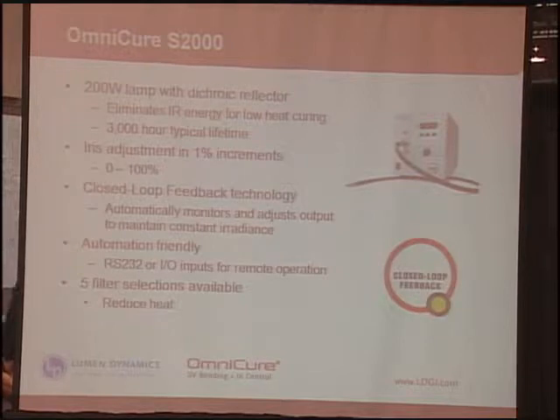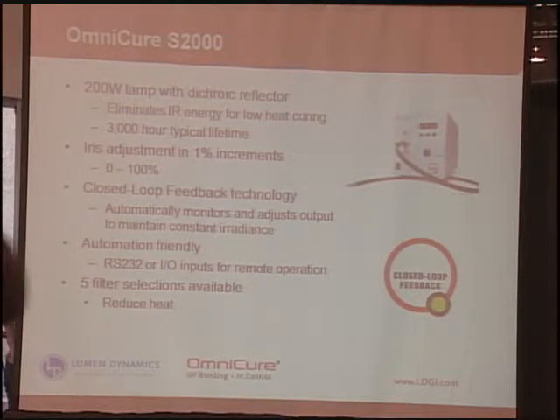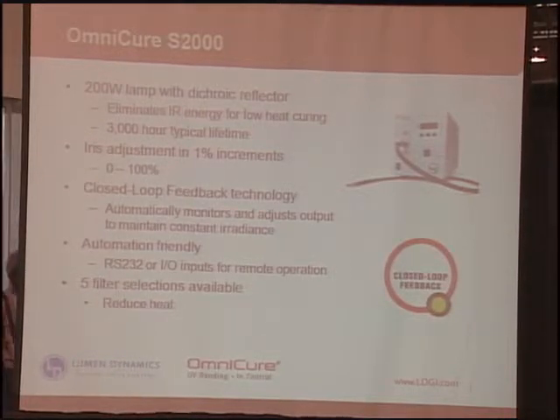Our lamp-based system is called the Omnicure 2000. It uses a 200-watt mercury lamp. It includes a dichroic reflector, and what the dichroic reflector does is it basically eliminates the infrared energy from the lamp, so it allows for reduced heat when you're curing your parts together. It's got about a 3,000 hour typical lifetime, and a peak irradiance of about 30 watts per square centimeter. Now you can adjust that output in 1% increments.